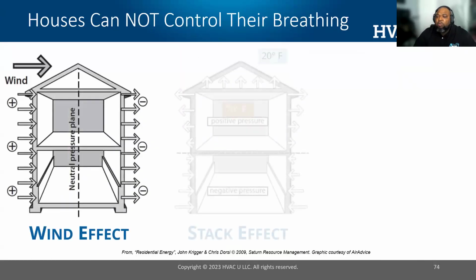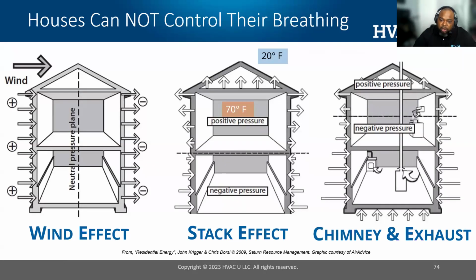Right? So we've got different ways where a house will breathe. We have wind effect where wind pressure will push air into and out of the building. You have stack effect where air will travel through the building based on a difference in temperature, and then you have mechanically driven air that leaks into the building. Well, you can't control any of these things. So it's not appropriate to let a house breathe to attribute ventilation, because you can't control which one of these things takes place. And you don't necessarily know where the air is coming from for respiratory health. So it's a practice that we don't do, and what we do, we build it tight and ventilate right. We make our house as tight as possible, and then we have a robust ventilation plan, an ERV, or some type of ventilation strategy that delivers enough CFM to control those indoor air quality issues. All right.